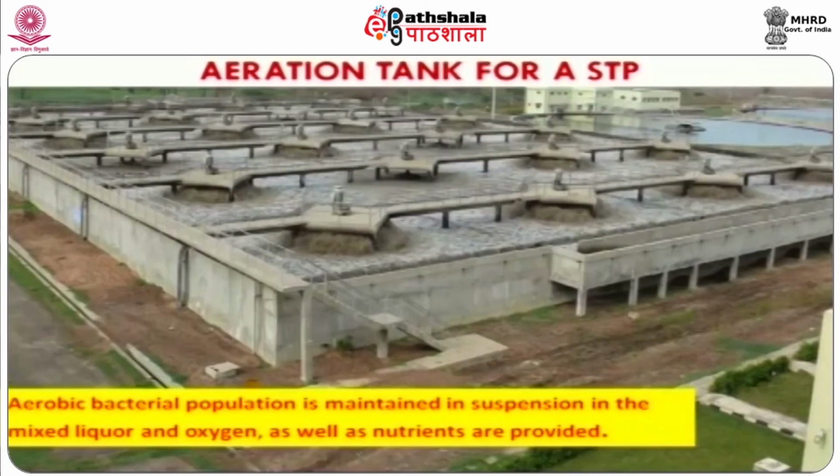In an aerobic system, molecular oxygen will serve as an electron acceptor. That is why we have to provide a minimum DO level of 2 milligram per liter to keep the entire reactor in aerobic condition. Otherwise, in addition to aerobic activity, some facultative organisms may flourish, if the DO level is less than 1.5 milligram per liter. Apart from that, we have to maintain adequate turbulence within the reactor to avoid settling of mixed liquor that will be generated during aerobic activity.